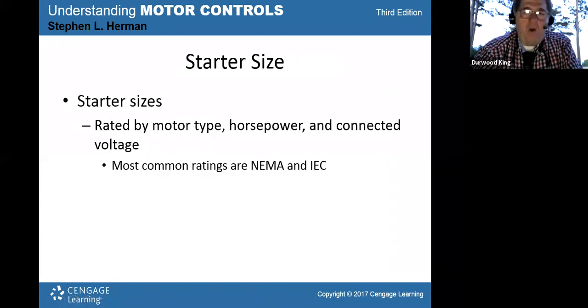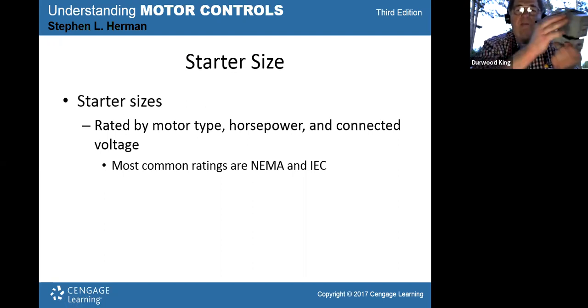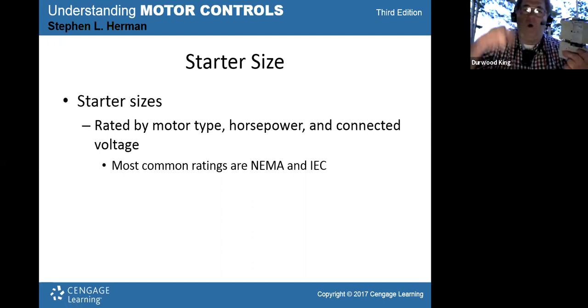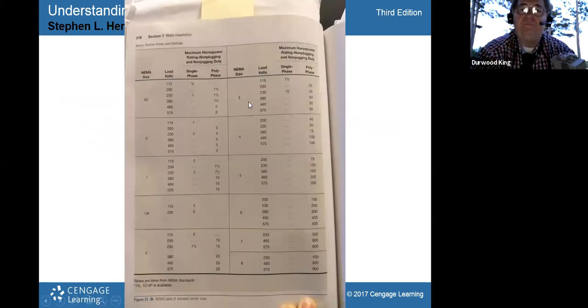Okay. Starter size. So how big of a starter can it be? It's going to be a NEMA size, a NEMA 0 and a 1 or 2, whatever. So right here, your NEMA size 0 would handle these voltage rating motors at these horsepowers. A NEMA 0 could handle these voltages at these horsepowers if it's single phase or 3-phase or polyphase. Say over here, a NEMA size 4, it could handle a 460 motor at 100 horse. A NEMA 4, it'd be a whole lot bigger than what I got in my hand. A NEMA 5 could handle a 460 motor at 200 horse. And so that, everybody okay on that? Yeah. So that for NEMA, that's how you would use it.